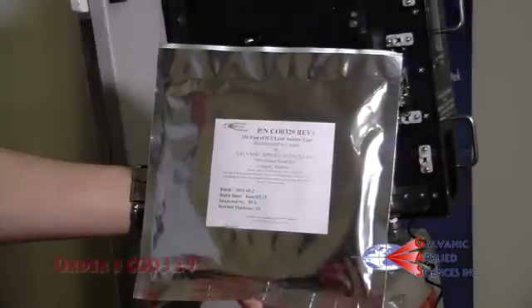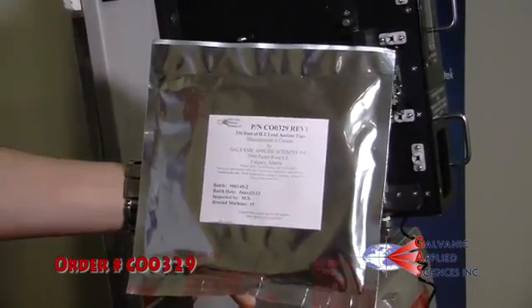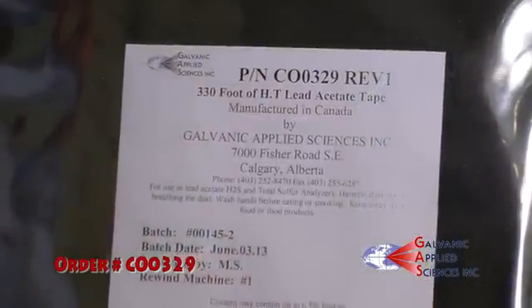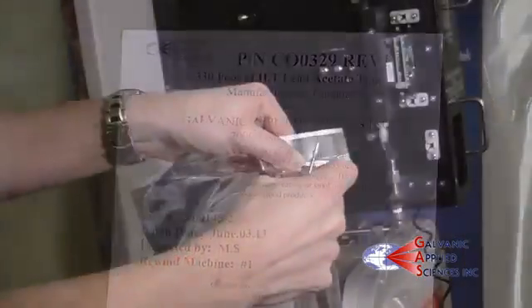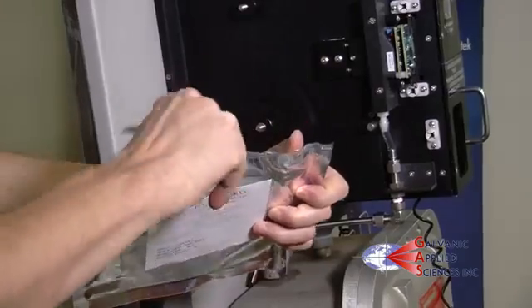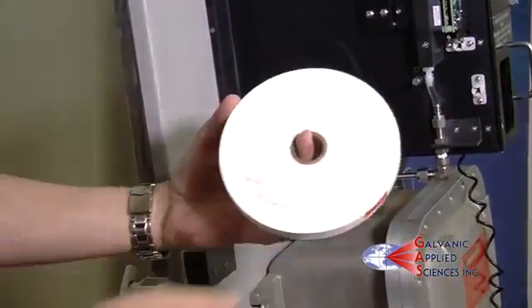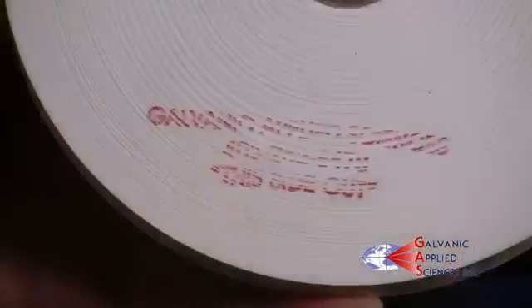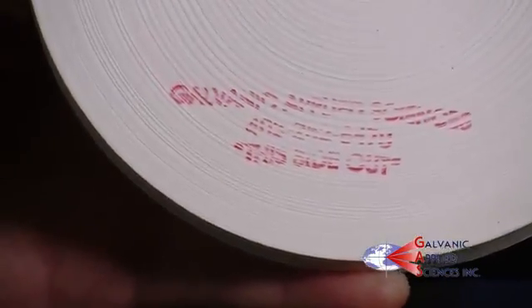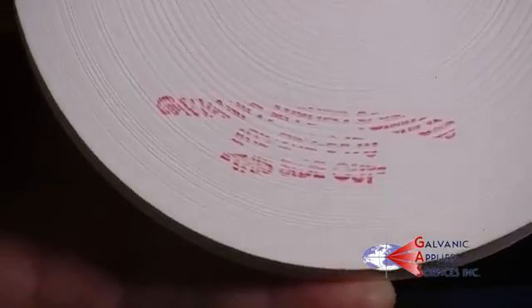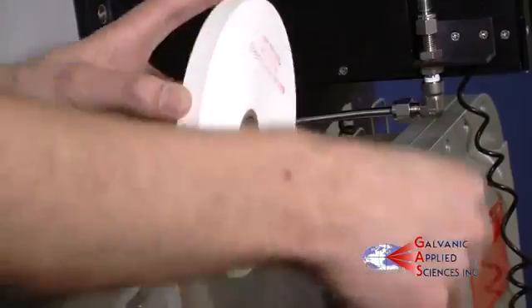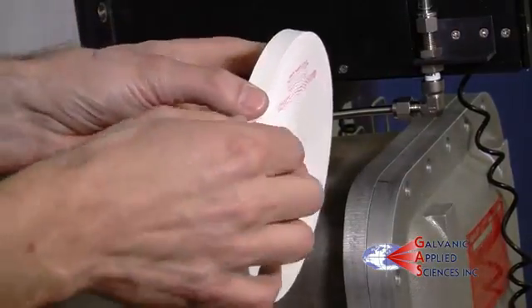Take a new package of Galvanic Applied Sciences lead acetate tape. Remove the tape from the package and make sure the stamp is facing away from the analyzer. Discard the outermost layer of tape as it can leave a mark that will cause a bad analysis.